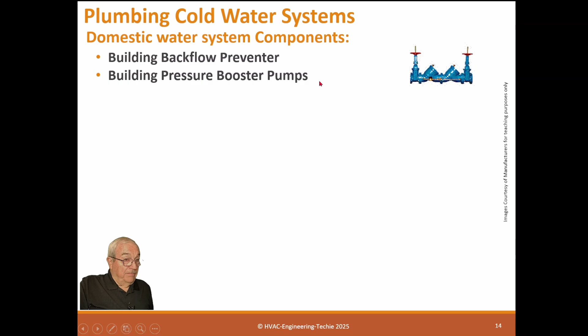And normally, remember that the main water coming into a building may have many uses. It may have fire water, domestic water, process water. It can be a lot of different waters coming in from one line. So these can get fairly large. You may require building pressure booster pumps if you have a higher building, mid-rise, or high-rise.